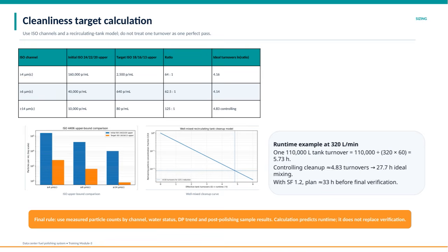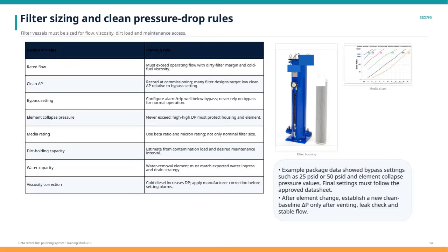These calculations predict runtime, but do not replace the need for verification to ensure the polishing system's effectiveness. Let's talk about the key considerations for filter sizing and clean pressure drop rules. When sizing filter vessels, it's important to account for factors like flow rate, fuel viscosity, dirt load, and providing adequate maintenance access. Starting with sizing, the rated flow capacity of the filter must always exceed the normal operating flow, allowing for a margin that considers a dirty filter condition and cold fuel viscosity, which increases resistance.